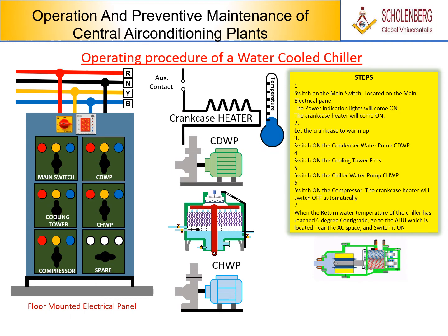7. When the return water temperature of the chiller has reached 6 degrees centigrade, go to the AHU which is located near the AC space, and switch it on.